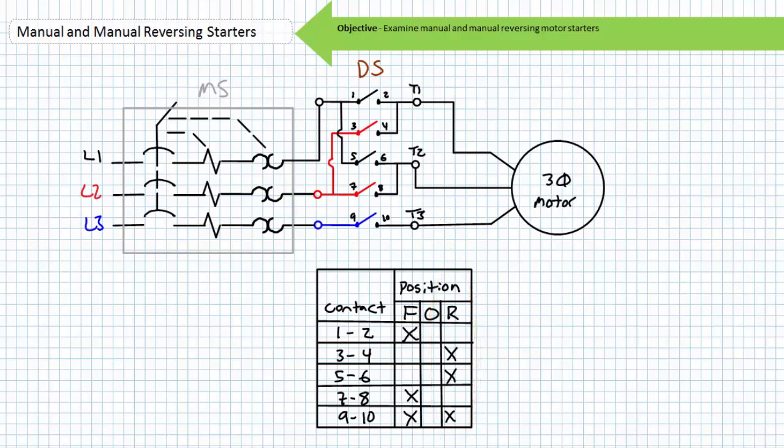Importantly, this pairing of a manual motor starter and drum switch necessitates that the motor starter be the one and only device that makes or breaks contact, not the drum switch. Drum switches are ordinarily not rated to make inrush current, nor are they designed to break full load current. The drum switch's only purpose is to determine the phase sequence applied to the motor. Operators must be counseled on the wise use of this combination of devices, otherwise equipment could be damaged and unsafe conditions could develop.